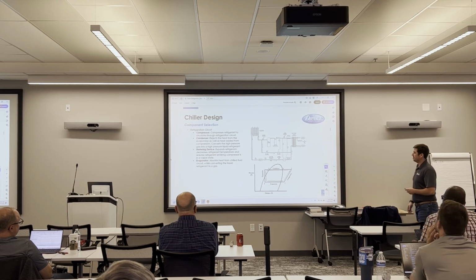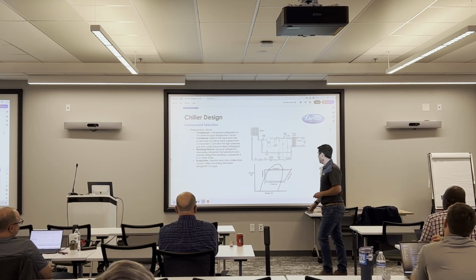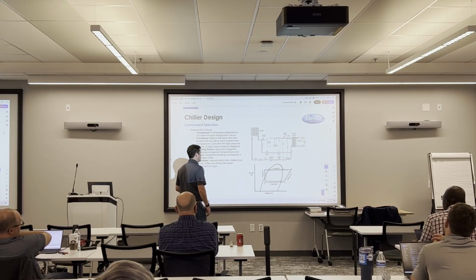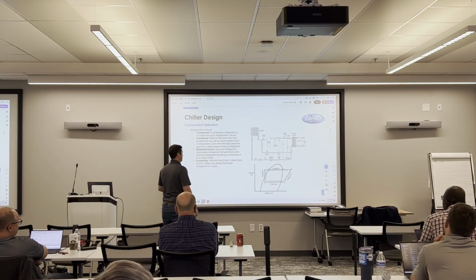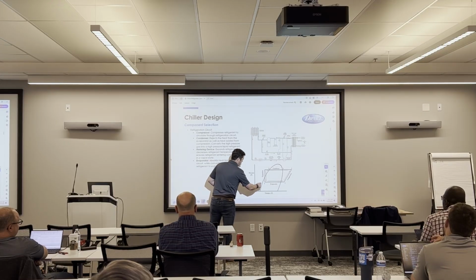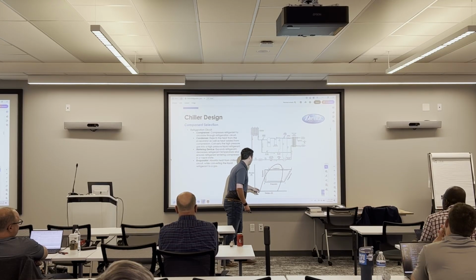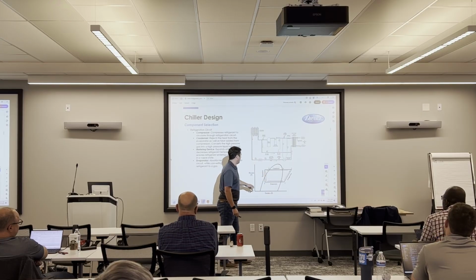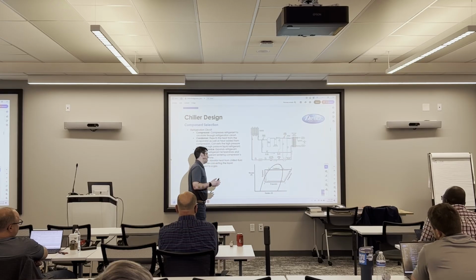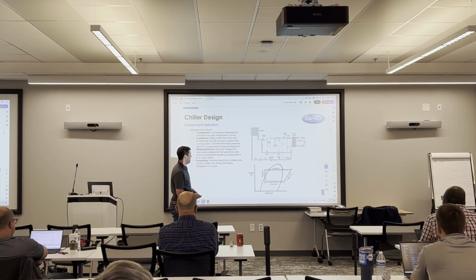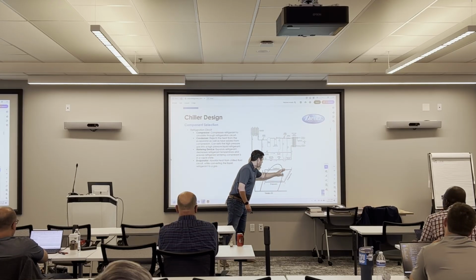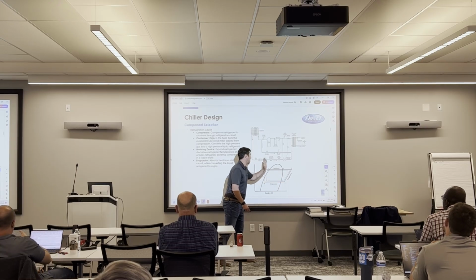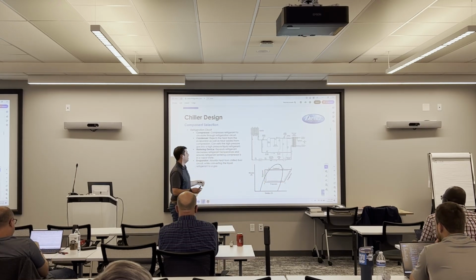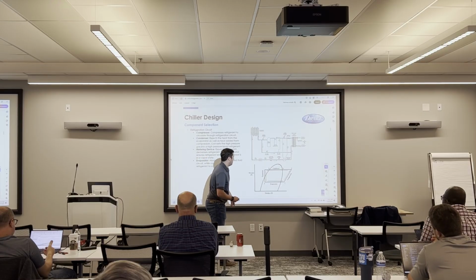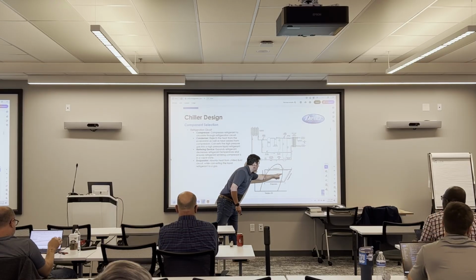This is just the refrigeration circuit on a PT chart. So we've got pressure versus enthalpy. You can think about this as temperature for convenience's sake. Again, just going through the components here. As we travel through the evaporator, we're underneath this dome right here. This dome represents refrigerant in a mixed state, so it's part liquid, part vapor. As we leave the evaporator, we want to make sure we leave outside of the dome. When you're outside of the dome, especially on the right-hand side, the refrigerant exists as a gas. As we leave the evaporator, we're picking up some superheat. The farther you are away from this curve is how much superheat you have.